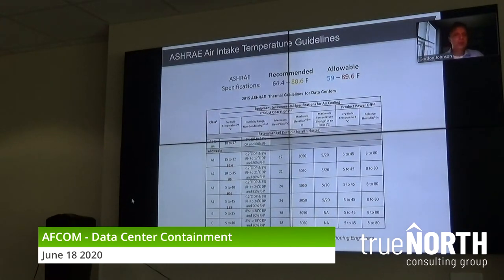I won't go through it all, except I do want to explain very briefly the difference between recommended and allowable, and also the class type server. So that first number, recommended, what ASHRAE is saying, and this comes back to how high should you be running the temperature in your data center. ASHRAE says you can run 64.4 degrees as your low temperature, 80.6 degrees as your high temperature.